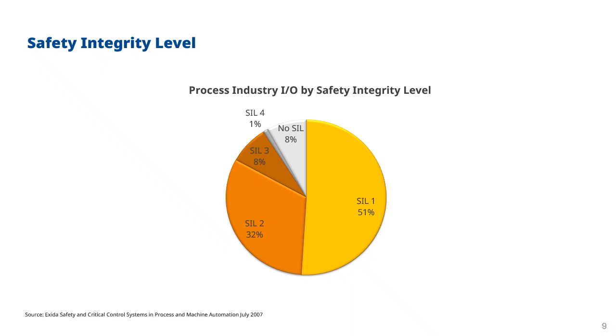SIL 4 is very rare. That can be covered under things like blowout preventers, and SIL 4 is also applicable in the nuclear industry. Just bear in mind that the nuclear industry has its own standards which aren't necessarily corresponding with the IEC 61511 or IEC 61508 standards. And SIL 4, of course, if you're talking about nuclear, then that's extremely onerous in terms of what's required. So SIL 3, bear in mind these figures come back from 2007. SIL 3 is about 8% of the market. So it's an attractive part of the market because these are quite complex systems and there's a lot of services around it, but it also requires a lot of additional work to achieve that.